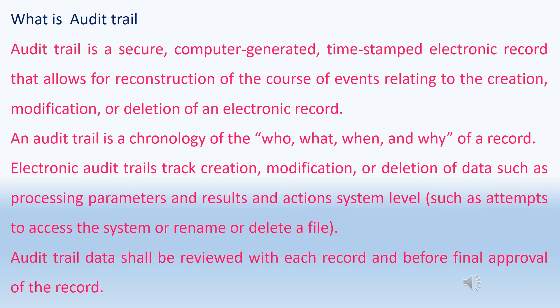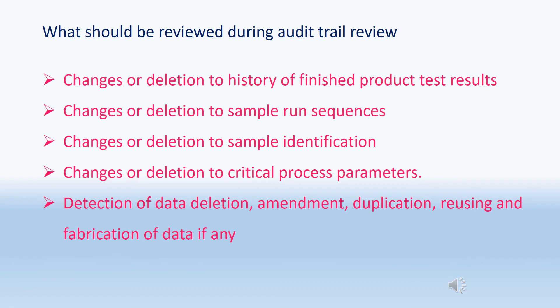When should the audit trail be reviewed? Audit trail data shall be reviewed with each record before final approval of the record. During audit trail review, the following should be reviewed: changes or deletion to history of finished product test results, changes or deletion to sample run sequences, changes or deletion to sample identification, changes or deletion to critical process parameters, and detection of any data deletion, adjustment, modification, duplication, reusing, or fabrication.